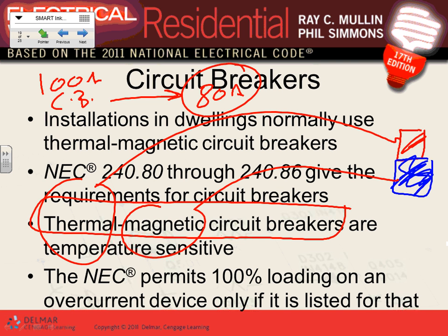If you have a 100 amp circuit breaker, I cannot load it more than 80%. Everybody is cool with that? Now, Jeff, when you open a 1,000 amp switchgear, unless the circuit breaker says 100% rated circuit breaker, you cannot continuously pull more than 800 amps out of this switchgear. Can I have thumbs up, chat, for that? This is a big concept.